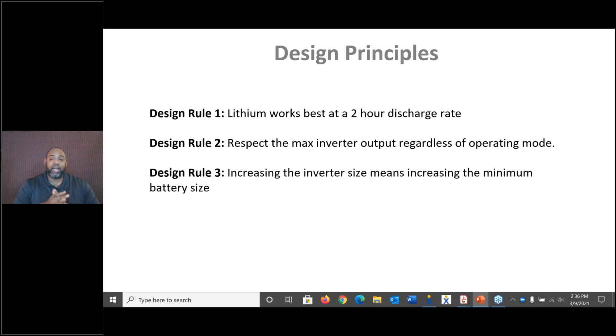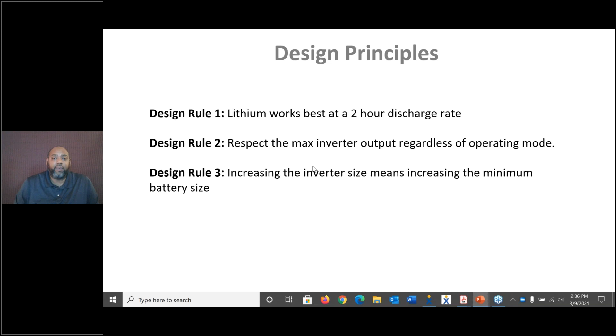I'm going to review some design principles, and there are 3 of them that I want to go over. Design rule number 1, lithium works best at a 2-hour discharge rate. Design rule number 2, respect the max inverter output regardless of the operating mode. And design rule number 3, increasing the inverter size means increasing the minimum battery size. And I will dive more deeply into this.